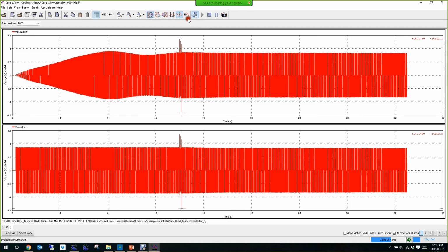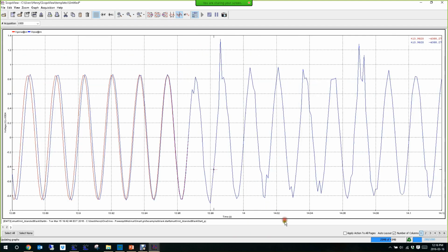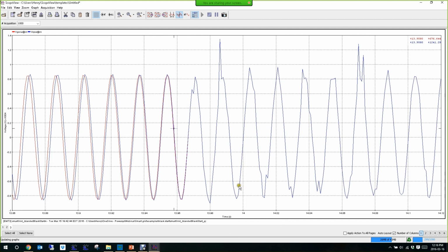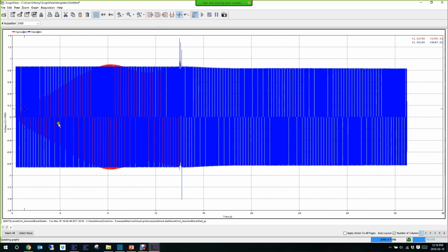At that point, we synchronized. If we put both of them together, we can see that at a certain point here, we synchronize them and they are the same. Here the stability of the machine can be discussed. It's actually an old governor and AVR. I'm sure it's possible to find a better one, but it's okay. The goal is not to discuss the control of the machine. Here we have one, it could be improved.